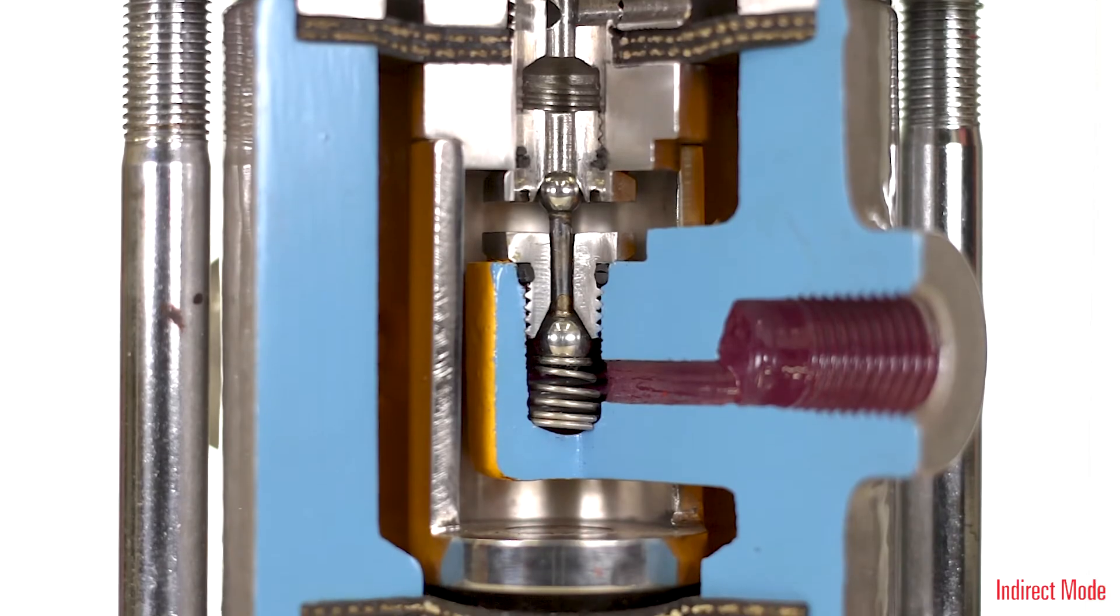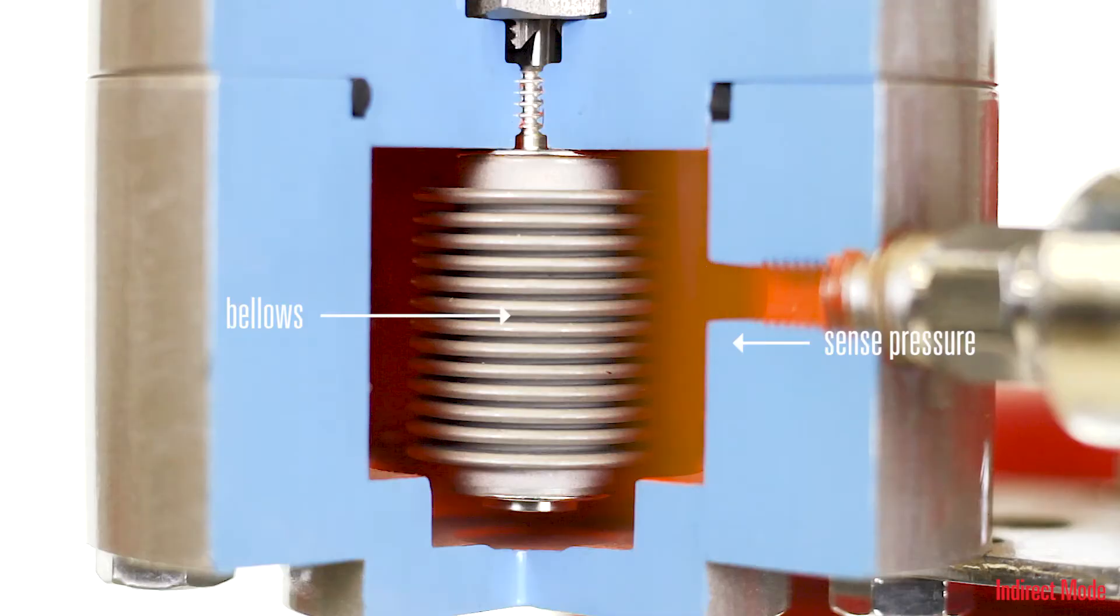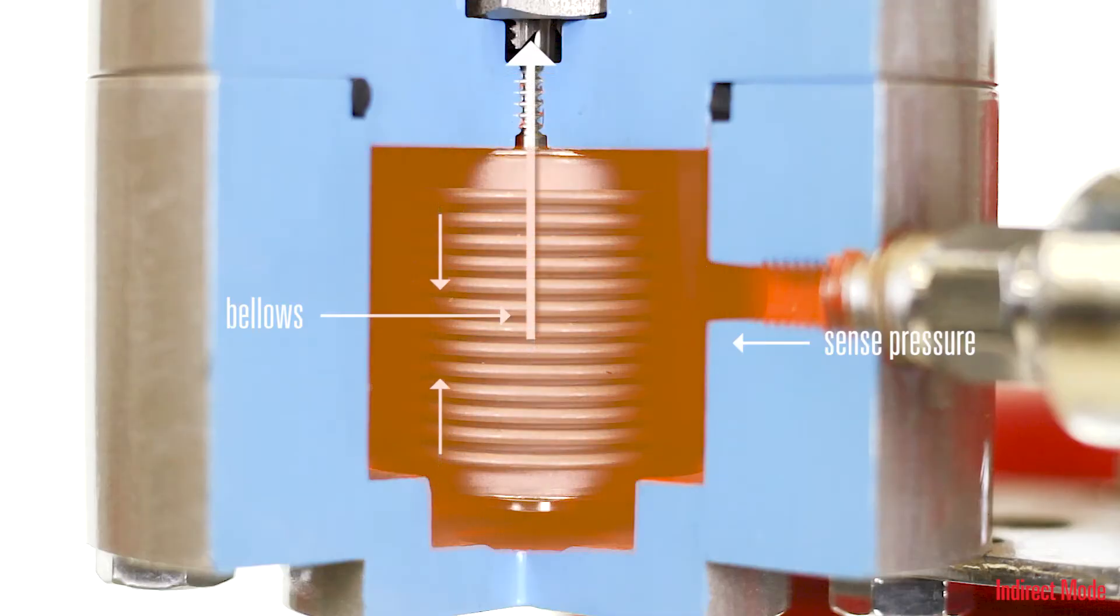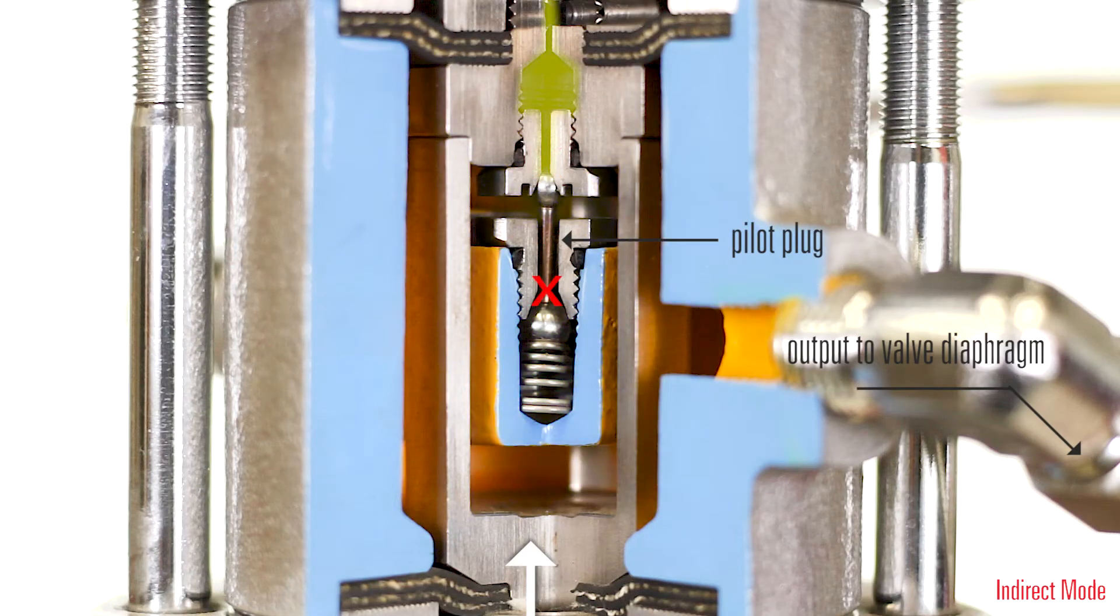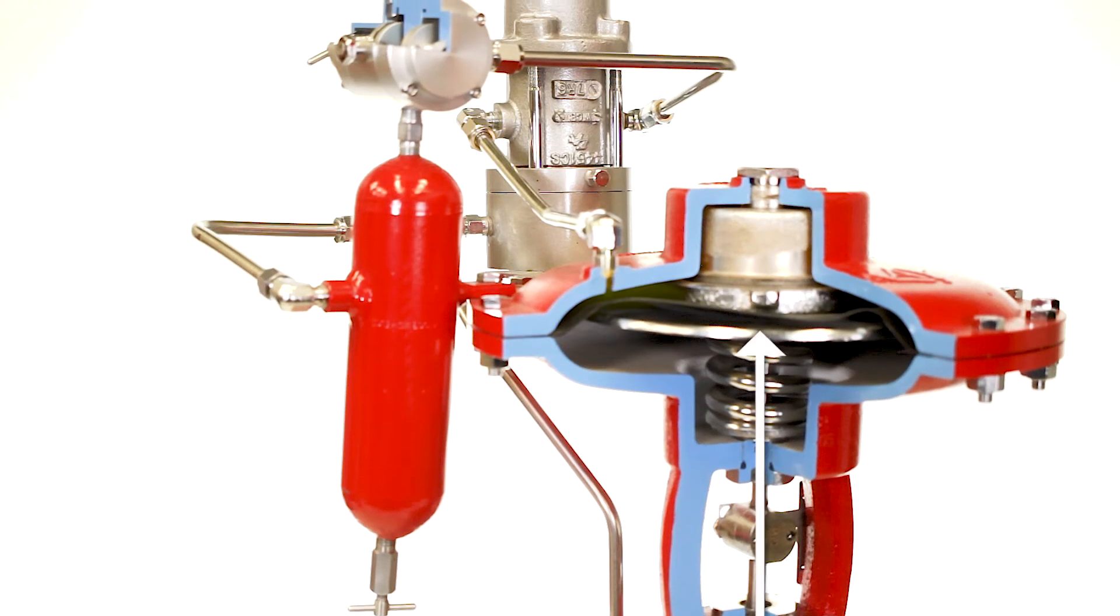In indirect mode, an increase in sense pressure compresses the bellows assembly up, which repositions the pilot plug, closing off the output to the valve diaphragm and opening the vent port. This will cause the valve to open.